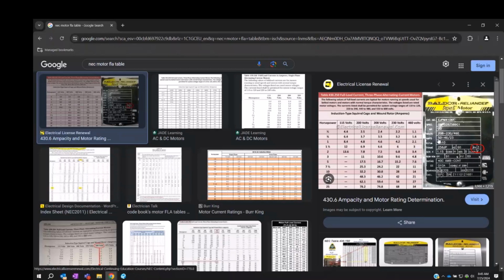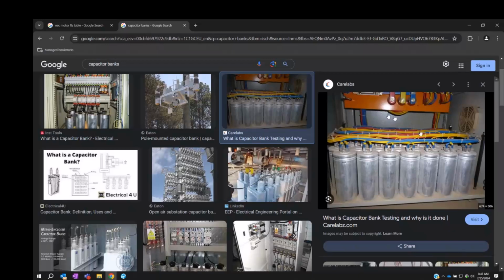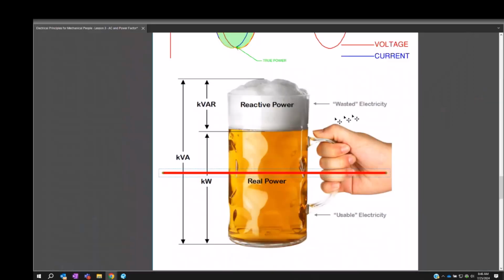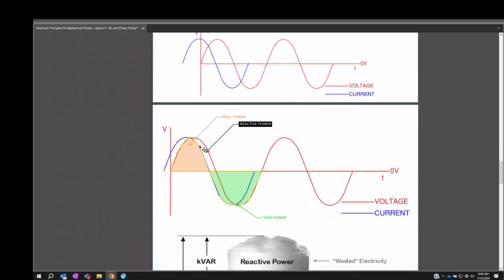Okay. In the happenstance somebody on YouTube needs this, there are such things as what are called capacitor banks. This would be more like what I'm looking at. So this is a step-in cap bank. Okay. So when a motor, let's just say a 600 horsepower, 480 volt motor, three phase, that's probably going to have a ridiculously large induction on it, which means it's going to have a very bad power factor. As the power factor gets worse, I don't want that bad power factor because it means I get less actual power out of that motor.